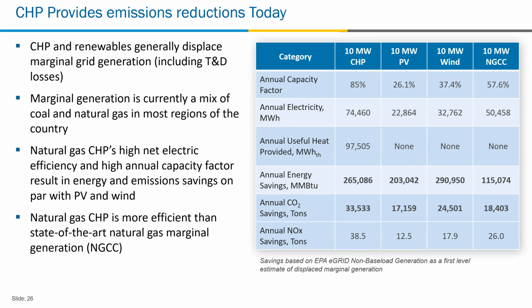Only CHP provides useful heat at the same time, and that results in CHP, a fossil fuel technology, saving as much annual energy in million BTU as the 10 megawatts of PV, wind, and the on-the-margin combined cycle system, along with comparable CO2 and NOx criteria emission savings. So CHP, even though it's natural gas based, saves as much energy and CO2 today when installed in a hospital or industrial facility as PV, wind, and the best natural gas generating technology out there. This is because of its high net electric efficiency and high annual capacity factor. Natural gas CHP in general is more efficient than state-of-the-art natural gas marginal generation, that combined cycle system.